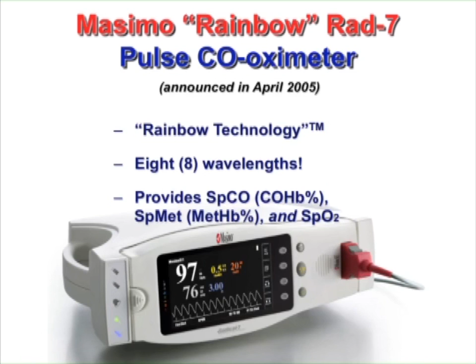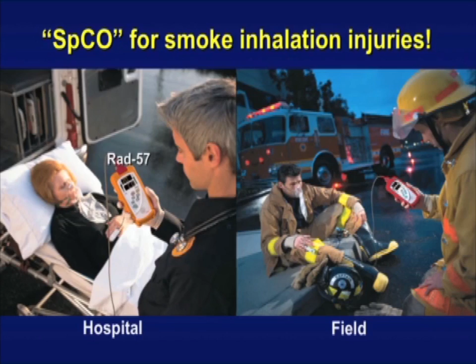We will get through the dyshemoglobins here, and then that's a good breaking point. It comes, as I said, in a handheld version, which can be used in the hospital and in the field, and these are very, very popular, in fact, almost universal in fire departments. I didn't realize until recently in talking to these guys that the people at greatest risk for carbon monoxide poisoning in building fires are not the people that were in the building. They have sense enough to get out. It's the firefighters. They have to keep going back in, and they're the ones that get exposed.